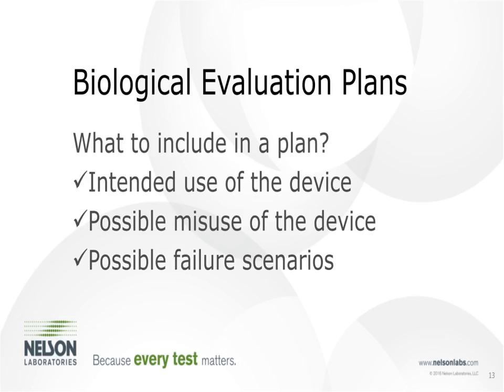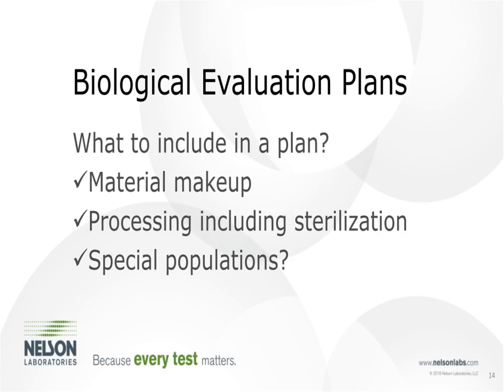And so it doesn't mean that you have to do a full-blown biocompatibility checkbox assessment on something that may or may not contact the patient. What it means is in this plan, you need to address possible failures that could happen, that you feel is a realistic possibility. And then you need to evaluate that failure by looking at the materials and the processing and the risks to the patient with its use, and be able to come up with that risk and how to evaluate that risk.